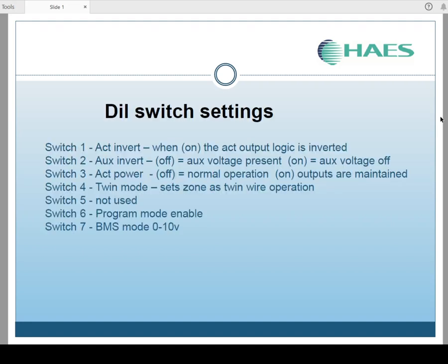So inside, on the bottom right hand side of the main board, there's a row of 7 little DIL switches. Switch number 1, when it's set in the on position, is the actuator invert. In the on position, the output logic is inverted, so the actuator will do the opposite of what you expect. Switch number 2 is the aux invert. In the off position, or default, the aux voltage is present to drive your magnetic windows. But you can invert that, so you can knock that switch number 2 on, and the aux voltage will be off and will go on in activation, so it works the other way around.